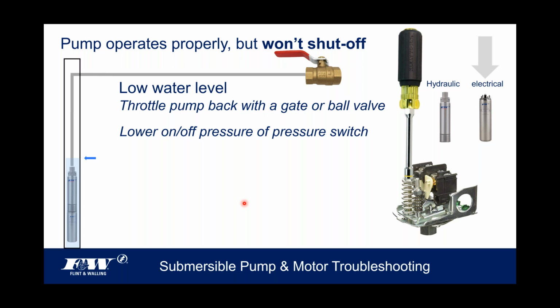While we're on the pressure switch, and before I get off of it, it's just a thought that came to me. There's a second tower on there. You'll see it in the bottom right-hand side of your screen. It's also spring-loaded with a hex nut on top. Most of the time there are no adjustments required there, 99% of the time. So while the tall tower can raise or lower both the on-off pressure simultaneously and maintain that 20-pound differential, the lower tower will either increase or decrease the differential.